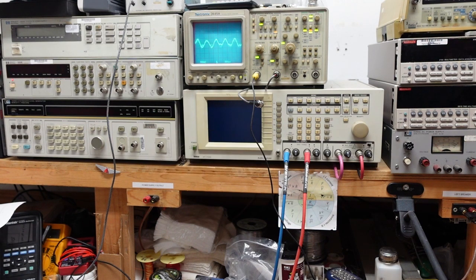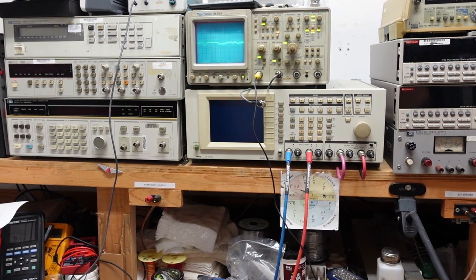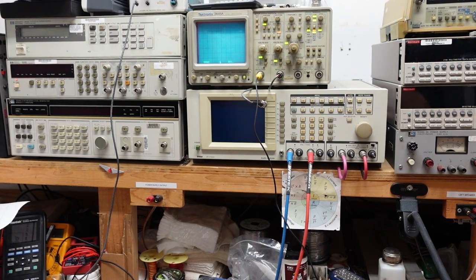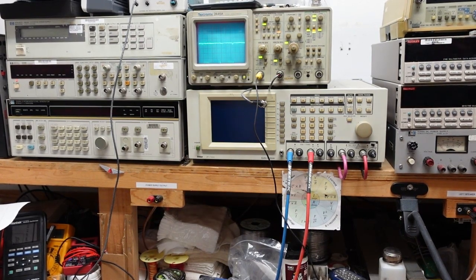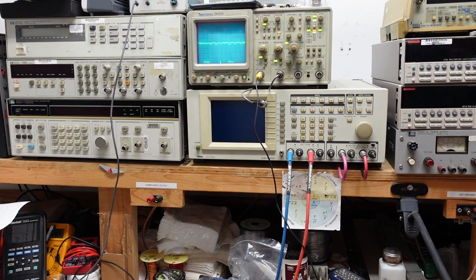Let's see. Okay, I'm at 5 microvolts here. You've got to have it right down in the dirt in order for this to be accurate. All right, now we go back to 106. What this does is it aligns the dial so everything falls where it's supposed to. Okay, we're at 106, so we've got to adjust our TC04. Okay, and there we are.